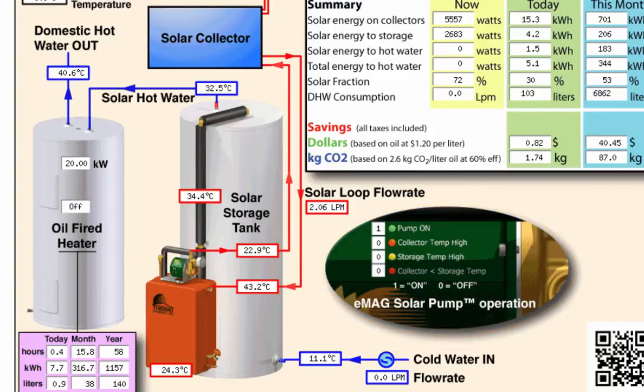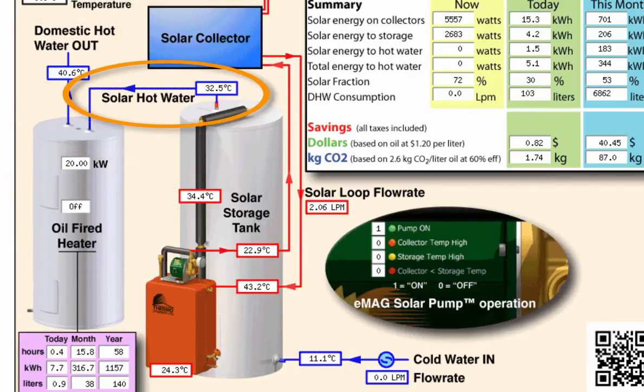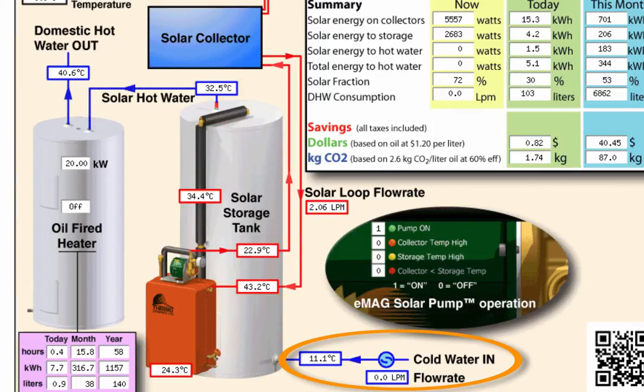As the water inside the solar boiler module heats up, it naturally floats to the top of the solar tank via this pipe here. This process continues such that the solar tank continues to heat as the sun shines. When hot water is drawn from the home's hot water heater, it will be replaced with preheated water from the solar tank instead of colder water from the main water supply. If necessary, the auxiliary heater will turn on and bump up the water temperature, ensuring that the water is always sufficiently heated.